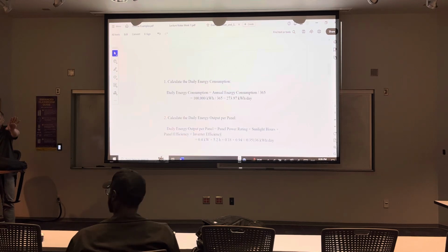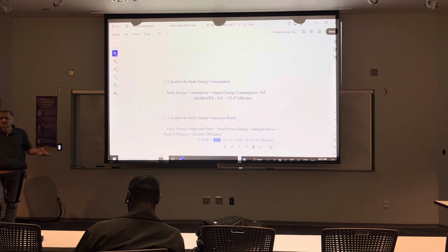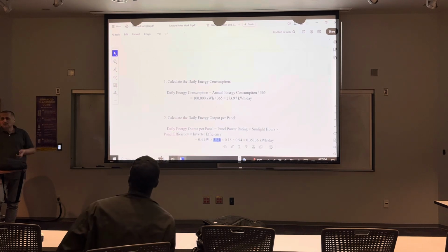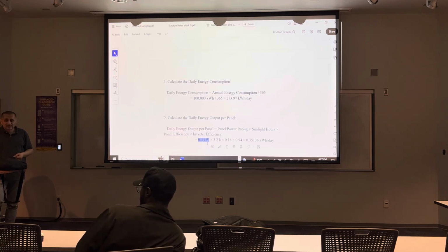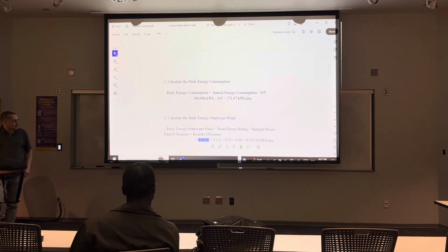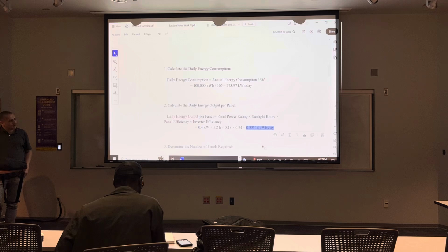You are the designer, so you can select any sunlight hour. Here 5.2 hours, this is fine, no problem. Maybe the city is just during the winter season is 5.2. Okay, 400 watt for each panel times the efficiency times the inverter efficiency. This value is in kilowatt hour per day.